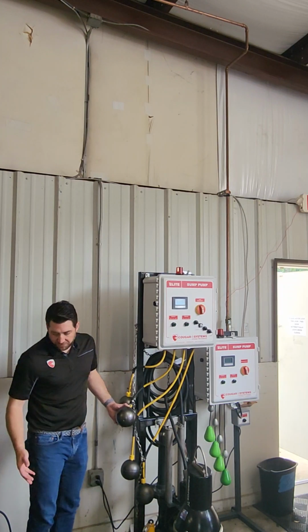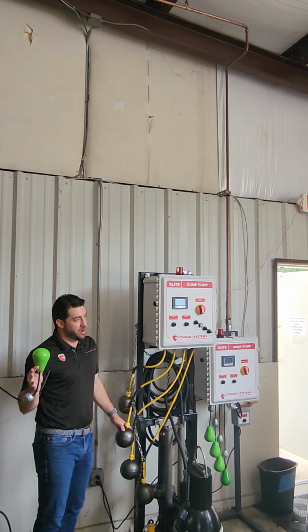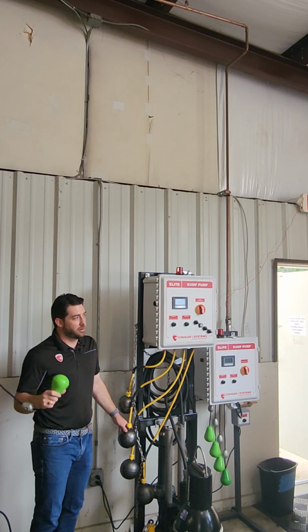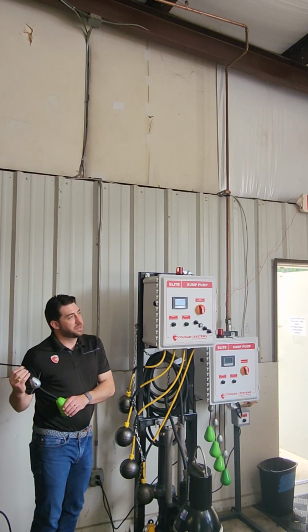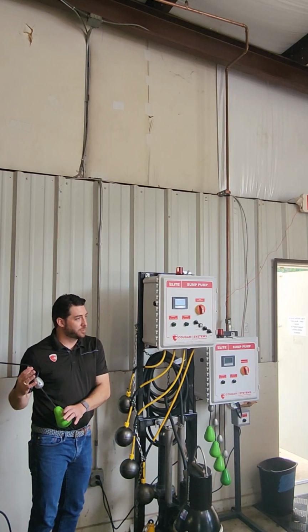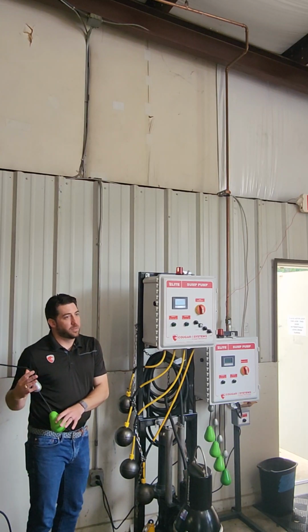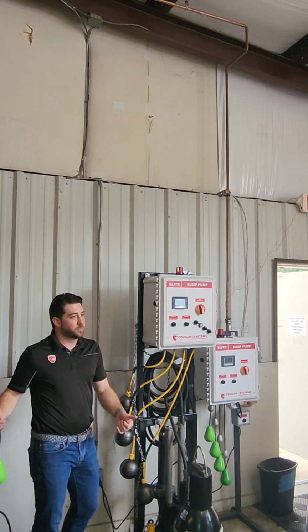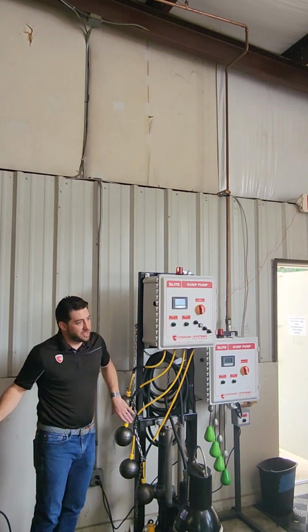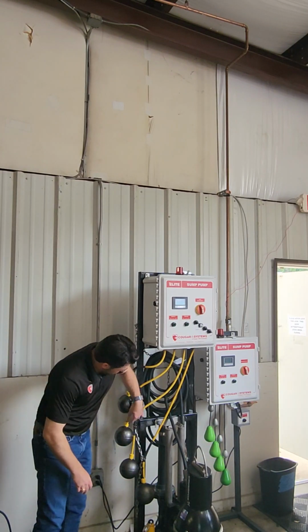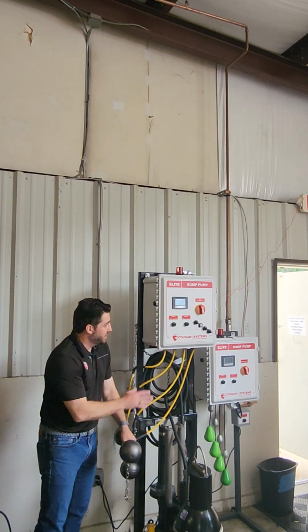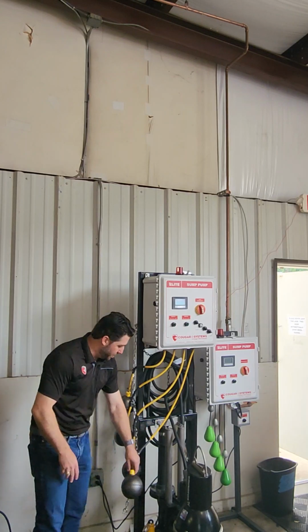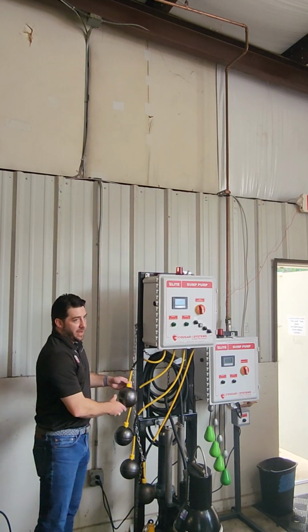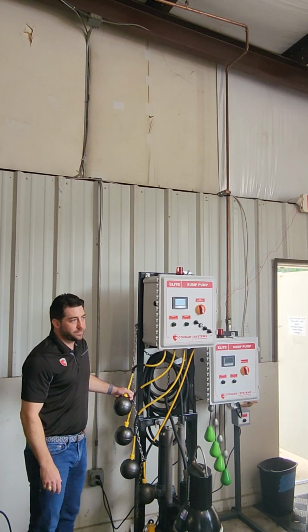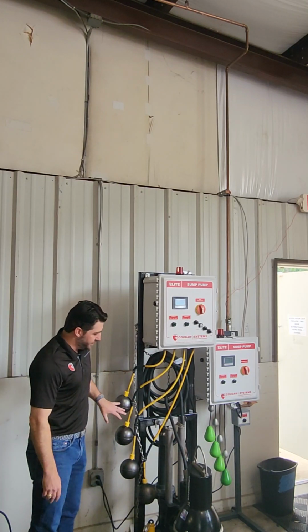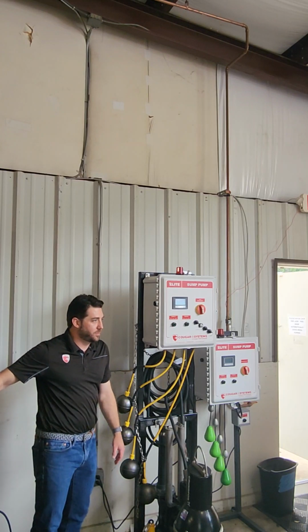The other thing that you'll hear when you're talking about float switches is wide angle and narrow angle. When you're doing a float switch like this from us, there's no difference in when it activates. They all activate the same way. The difference between narrow and wide, they kept the naming convention, but the narrow ones are made for control voltage, so they can't handle being wired directly through a pump. The wide angle are pump duty, meaning you could do a piggyback float switch and run a small pump on it. But with the mercury ones, they really do have a wide angle and a narrow angle. The narrow angle we would use for the first three because they're just doing controls. They're just telling the panel that there's water there, so they activate on a more narrow range. And this one would be a wide angle because we want that pump down, to be able to get a wider swing. So there is a little bit of difference in the float switches, not a lot. These, we only buy the narrow angle for anymore.